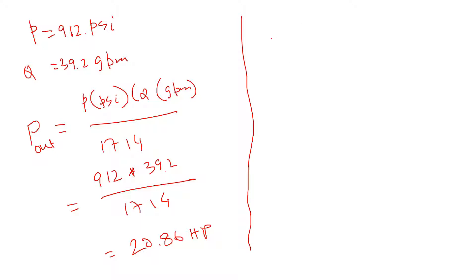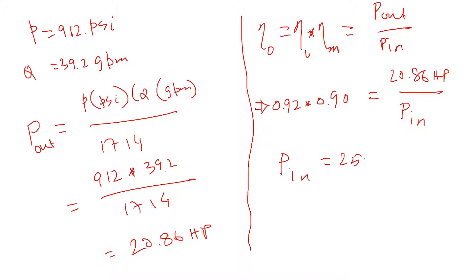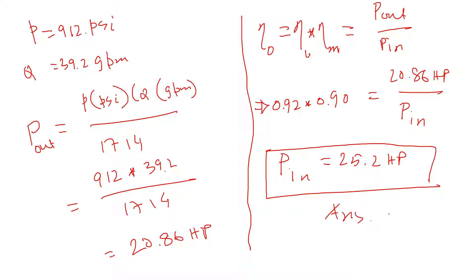Now calculating input power. Overall efficiency equals volumetric efficiency × mechanical efficiency, or equivalently output power divided by input power. With η_V = 0.92 and η_M = 0.9, and output power of 20.86 HP: input power = 20.86 / (0.92 × 0.9) ≈ 25.2 horsepower. That is the answer to question B.